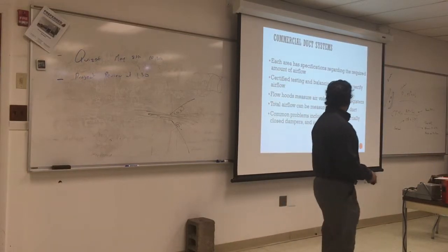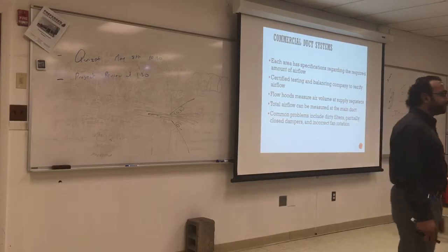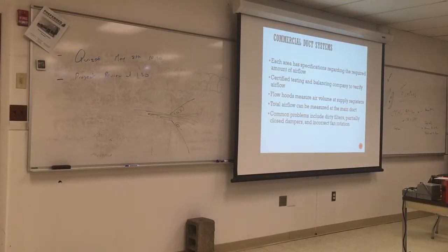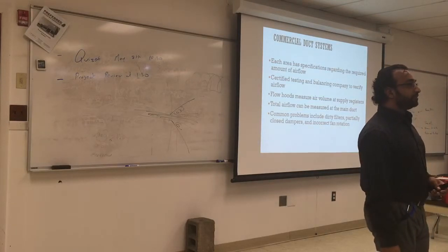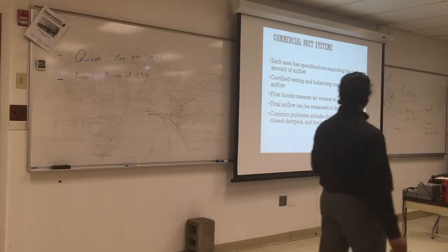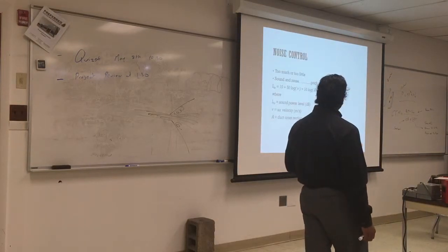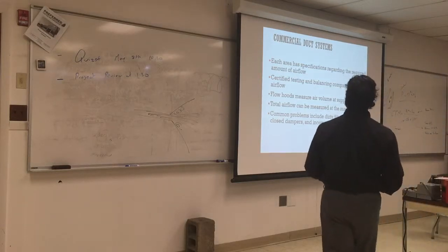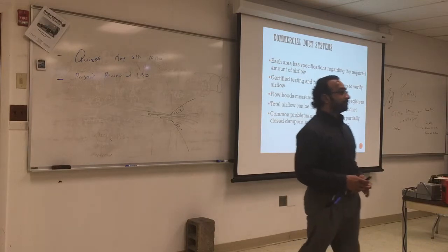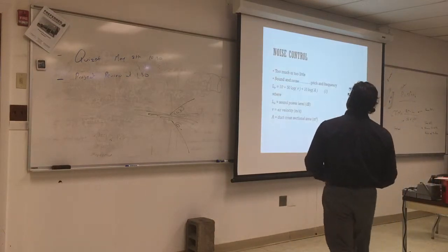Common problems include dirty filters, partially closed dampers, and incorrect fan rotation. Incorrect fan rotation is very common. Sometimes the fan is not turning the right way and it could be a problem with the air flow. Some dampers are not closed fully, so that will leak some air and disturb your pressure flow in the duct system. Somebody might replace the fan and put the blades the wrong way. That's why they always tell you which way is outside and put an arrow on it. It does happen sometimes when you replace the fan and put it the wrong way and reverse the flow.